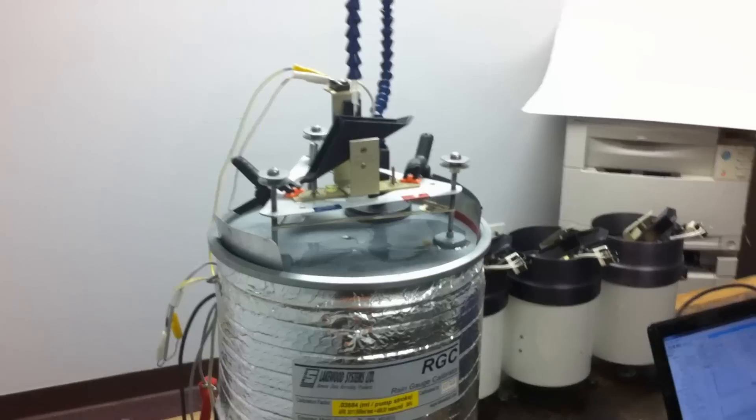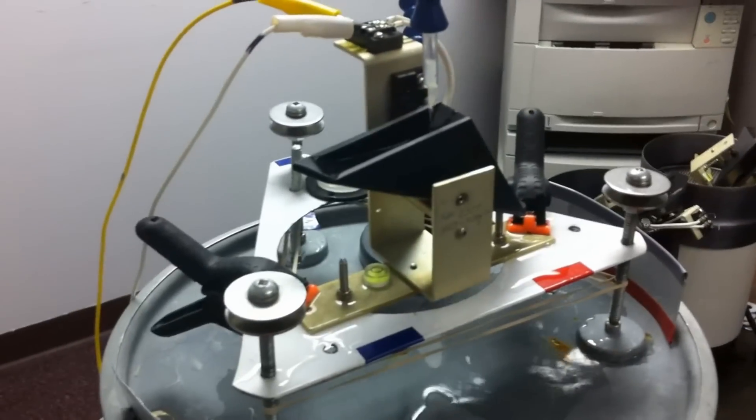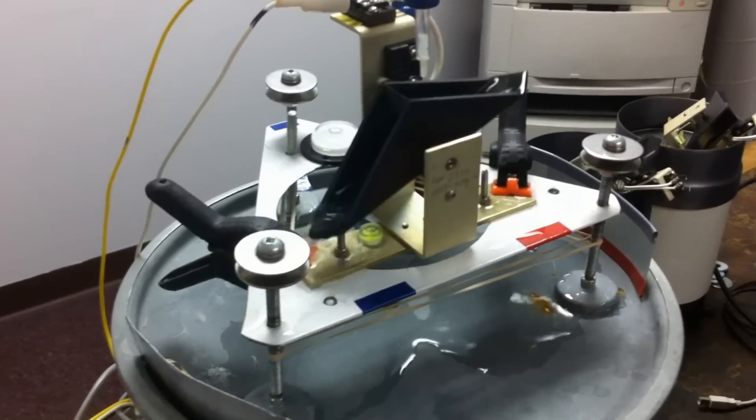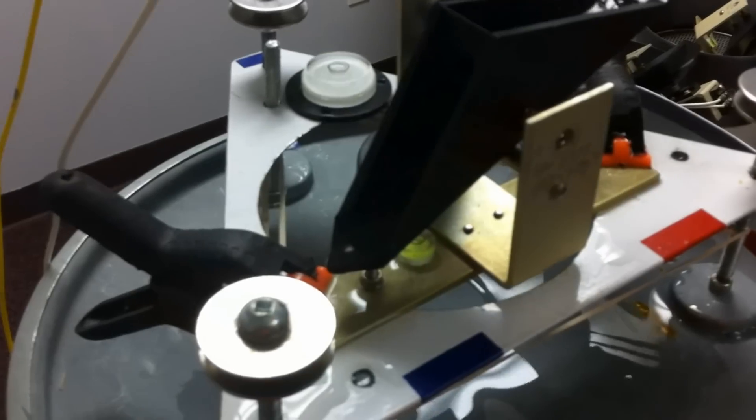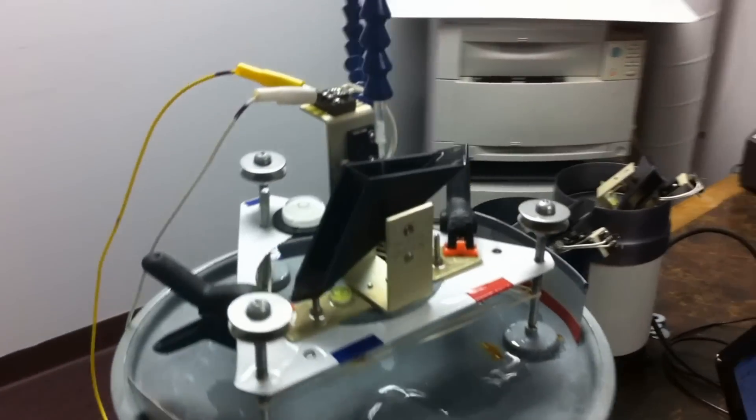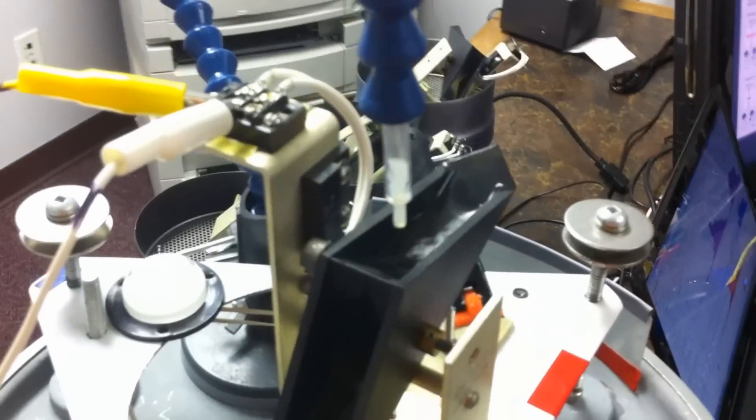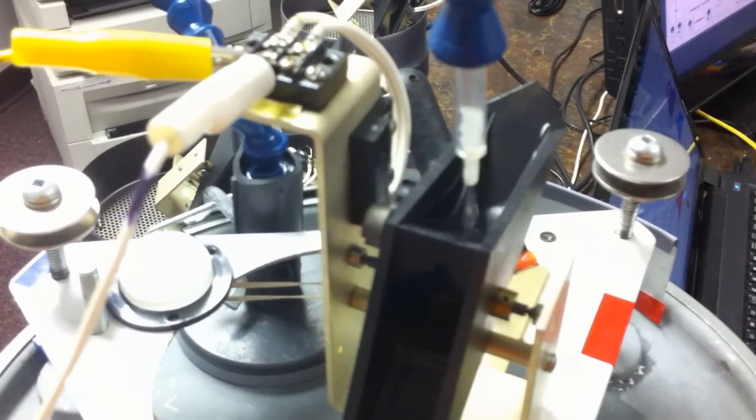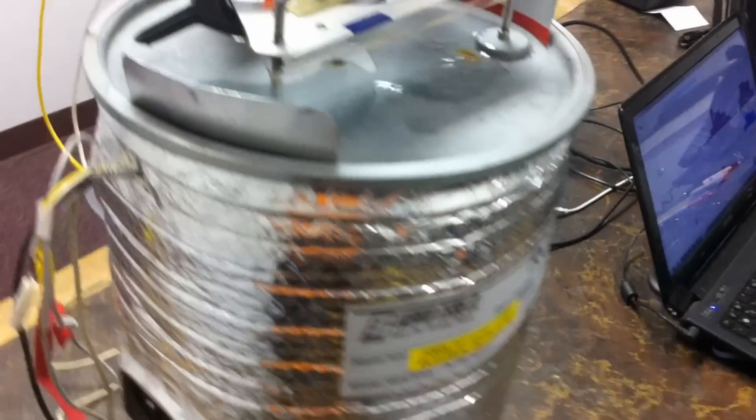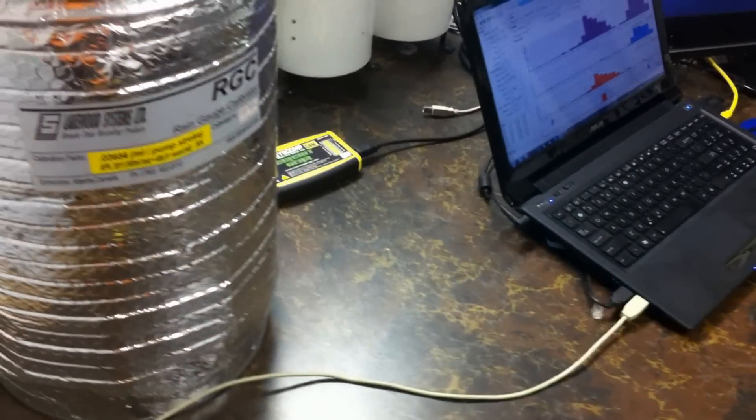This is a video overview of Lakewood's digital calibrator. We currently have a tipping bucket gauge attached to a leveling platform here. The three bolts allow us to level the gauge accurately to the bubble level that we can see here. This rain gauge calibrator is set up right now to put a very accurate amount of water into each side of the tipping bucket. The bucket is then wired into a monitoring control board, and that control board is plugged into the USB connector on the computer here.